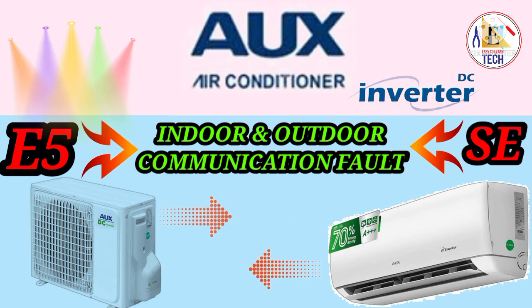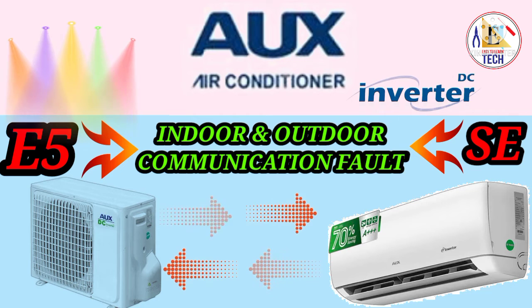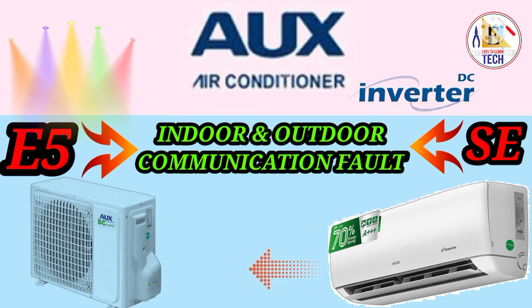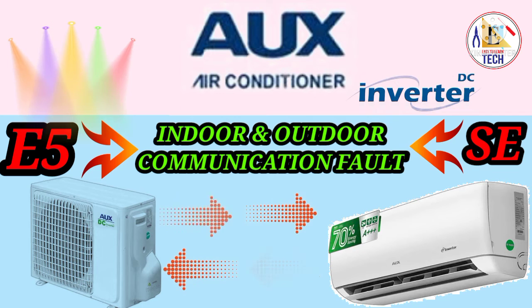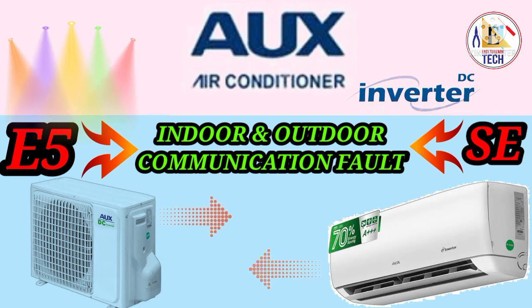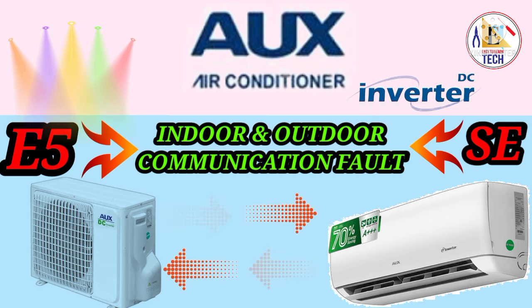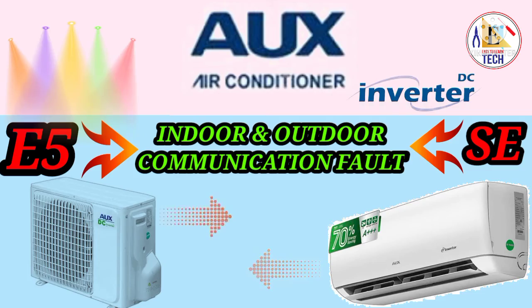Again, if you are getting the same error, it means there is an issue in the indoor PCB or outdoor PCB. First of all, you have to check the indoor PCB out. It should give a DC supply of 9 to 24, and you have to check the same in the outdoor. There should be 9 to 24 DC volts coming out from your outdoor unit. If it is not coming from either the indoor or the outdoor, it means you have an issue with the PCB. You have to change the PCB and you will get the solution for the error E5.